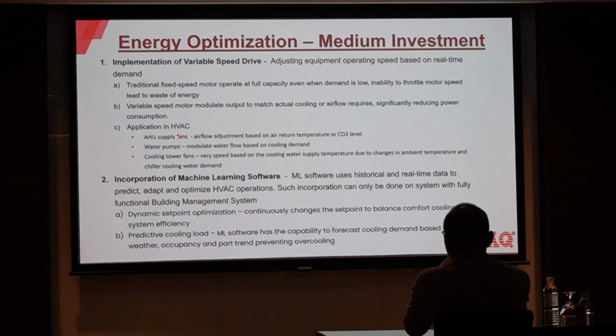Right, so application in HVAC. We can incorporate the VSD on AHU supply fans. In most cases, the AHU are neglected. They just run fixed speed, they just supply the air. But with the VSD, we will be able to throttle the air supply to whatever is required. And then on the pumps, modulate water flow based on the cooling demands, and cooling tower fans. So with the VSD, it basically helps to meet the actual demand.